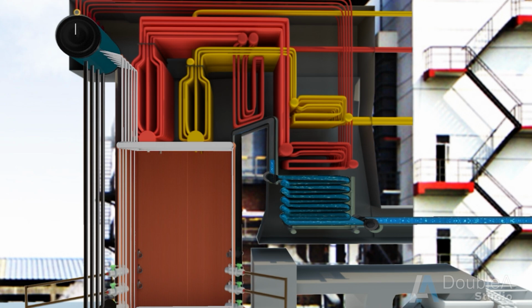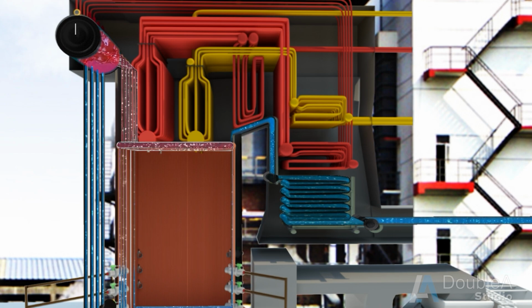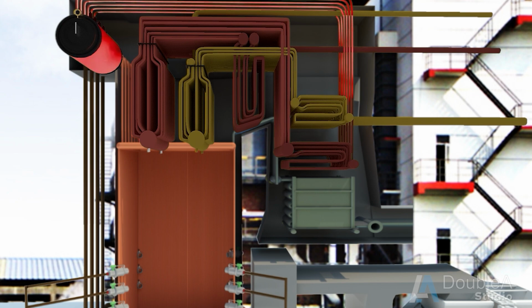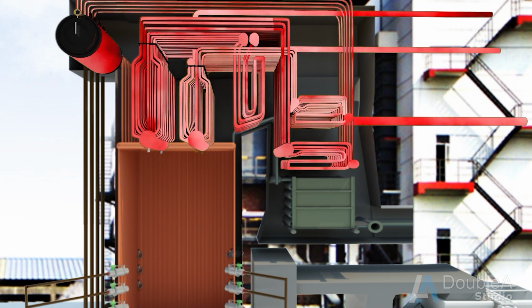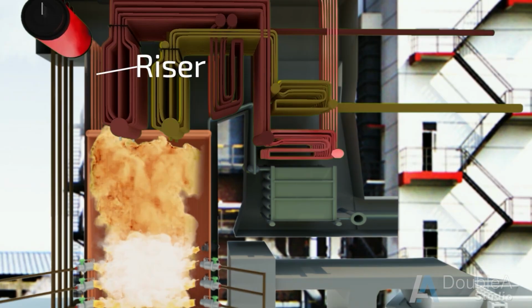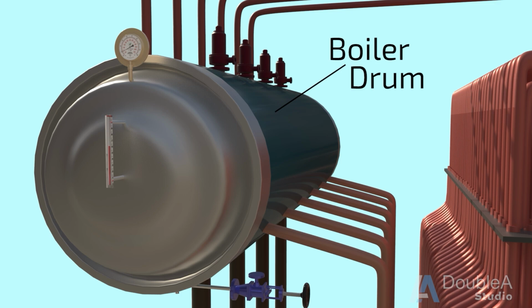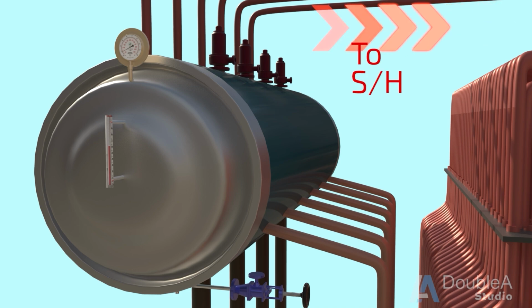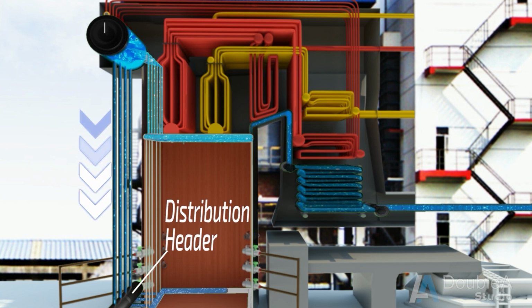Water from distribution headers enters all the water walls. It gets heated up in the furnace area and partially converts into steam. This water and steam mix runs through the risers up to the boiler drum. The boiler drum is a high-pressure vessel which separates steam from water with the help of drum internals. After separation, steam is sent to superheaters for further heating and water is sent to the distribution header through downcomers, and the cycle is thus repeated.